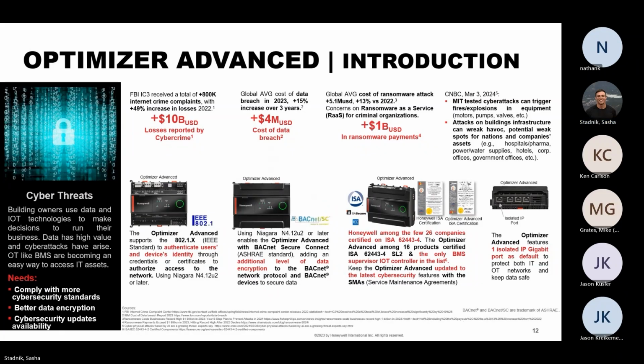But what is the problem? Having integration. My question to you is, how many times do you find a building that's only running BACnet? What's going to happen with the other side? Is it encrypted? No. LonWorks? No. So is it good if you have a building running BACnet all over it? The moment you start to integrate other protocols, which is why you have a JACE or an advanced controller, guess what, that is also an open door for anyone to bridge and come in. So BACnet Secure Connect is actually encrypting data between two BACnet devices, but only BACnet. Whatever you have attached to the controller on the other port, it's an open switch port.